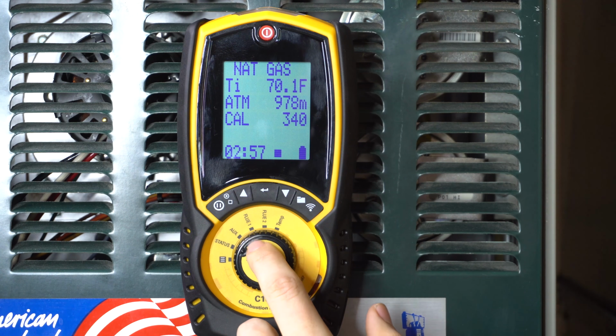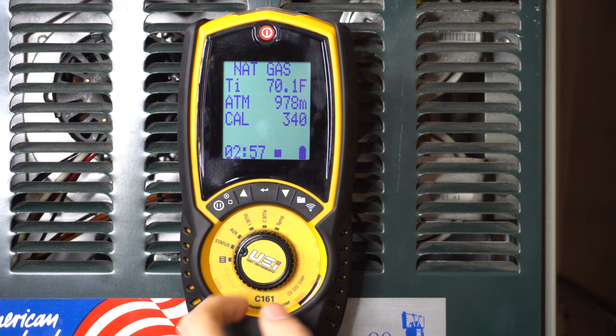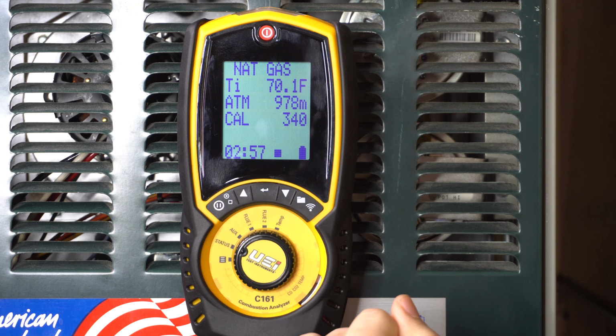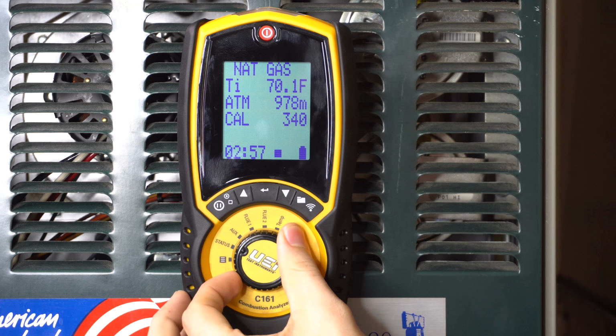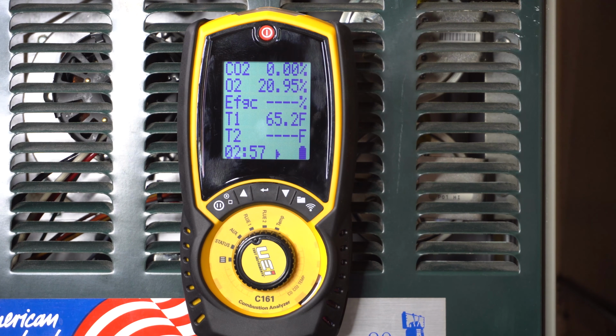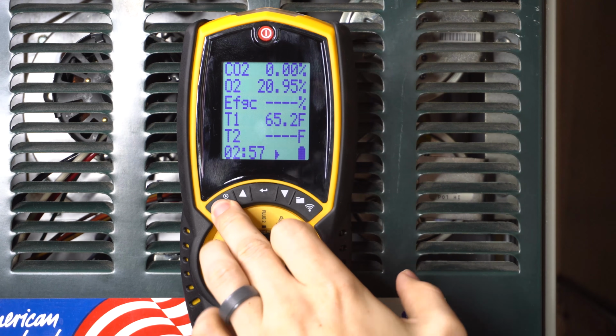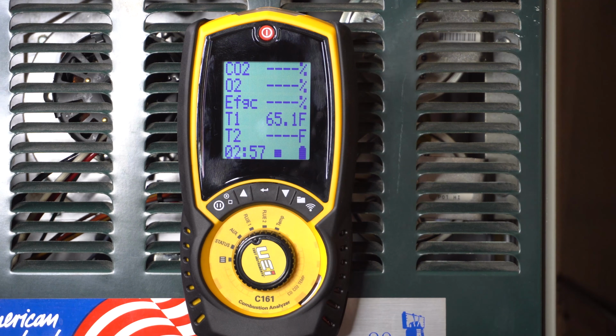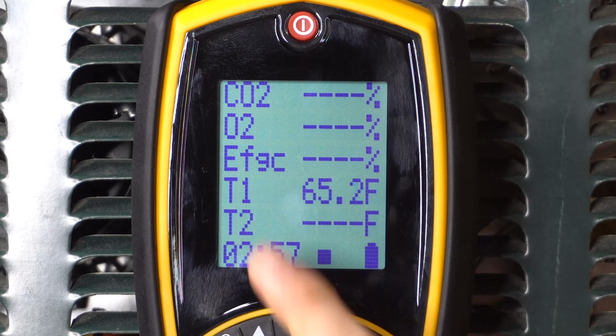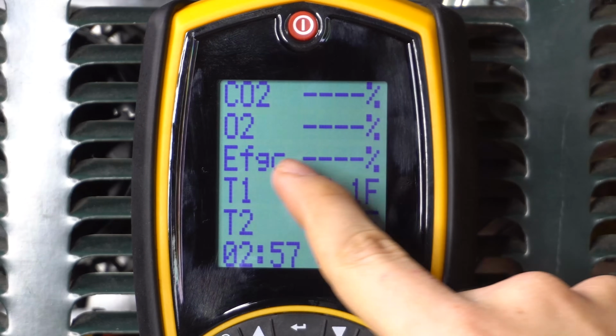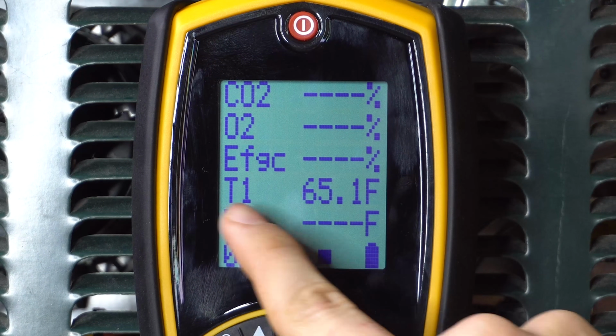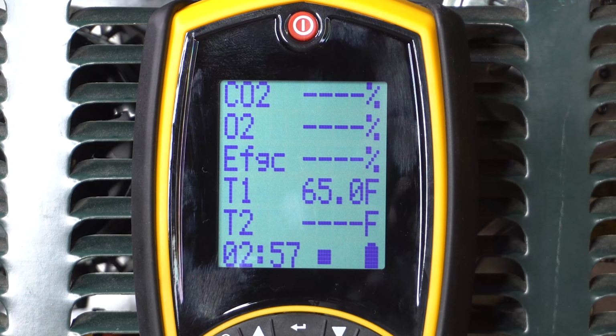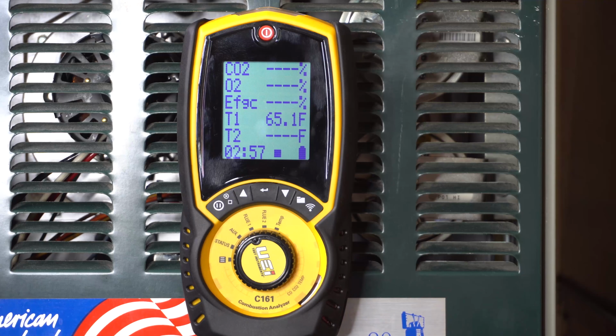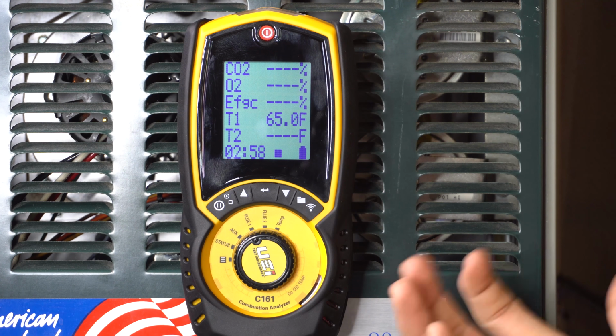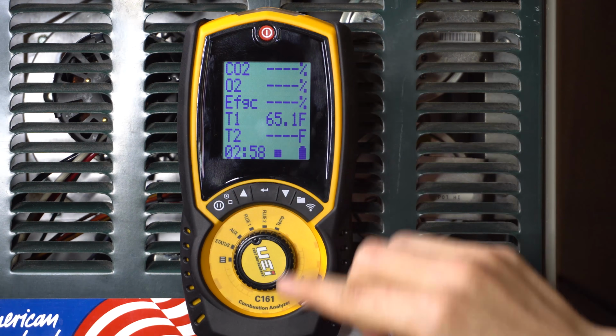Our next three settings on the menu are AUX, Flue 1, and Flue 2. And whenever you switch to any one of these three, the pump automatically starts. Let's just start with Flue 1. There you go, the pump fired up. And I'm going to go ahead and pause it for now by hitting and holding the pause button. So CO2 is for carbon dioxide, O2 is for the oxygen, EFGC is efficiency, gross calculation, T1 and T2 are temperature 1 and temperature 2. The reason I don't have temperature 2 showing up here is simply because I don't have the second temperature adapter plugged in, and I usually don't use it. So that's the first menu, and we'll see these numbers filled in after I actually fire the furnace up.